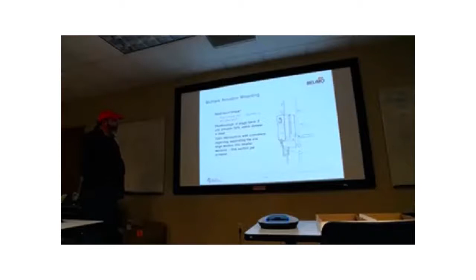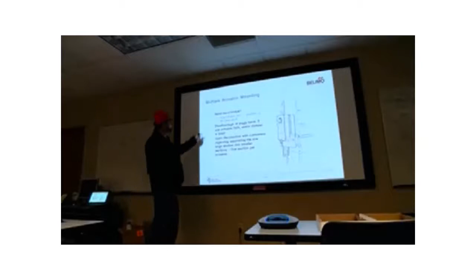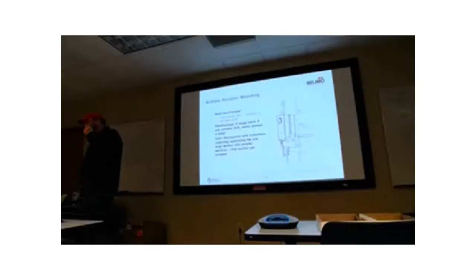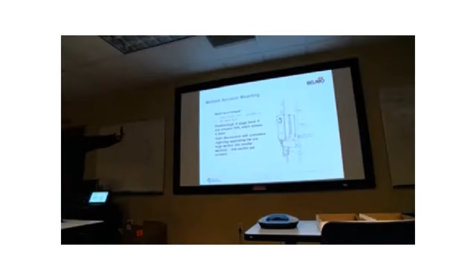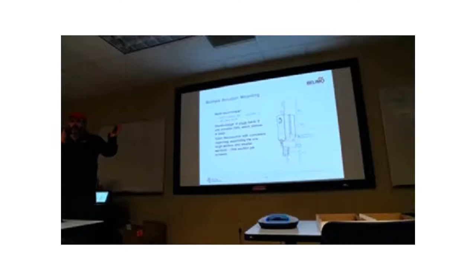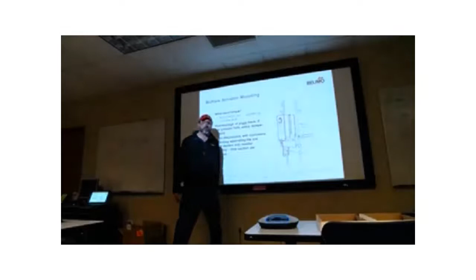All right, here's one of the more important parts of this presentation. We talk about multiple actuator mounting, meaning mounting actuators on the same shaft or mechanically linked in some way. There could be two separate dampers linked by a crank arm and a push rod assembly, or two damper actuators on the same shaft like this. What we recommend, and this has probably been the case for at least 9 or 10 years now...